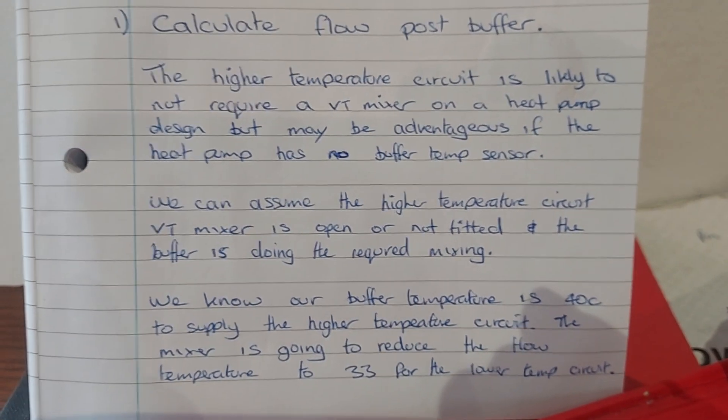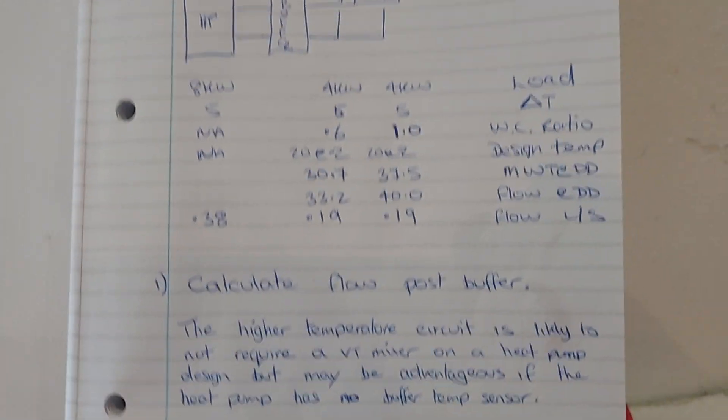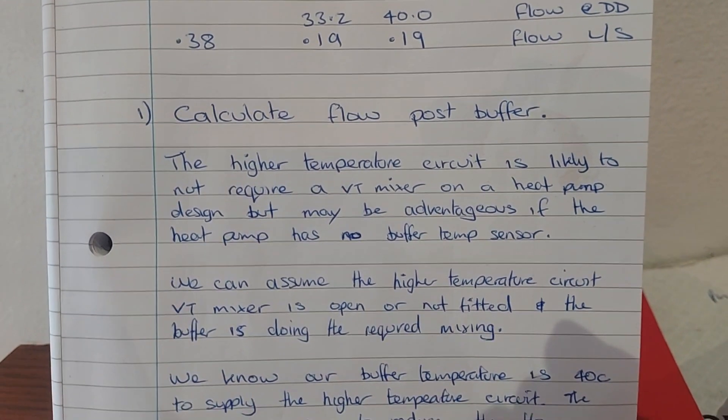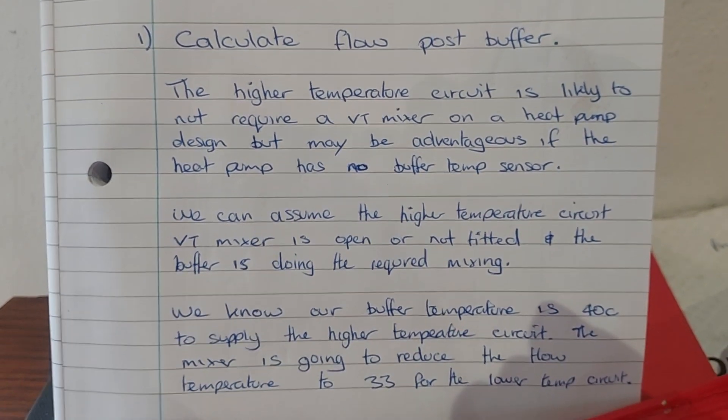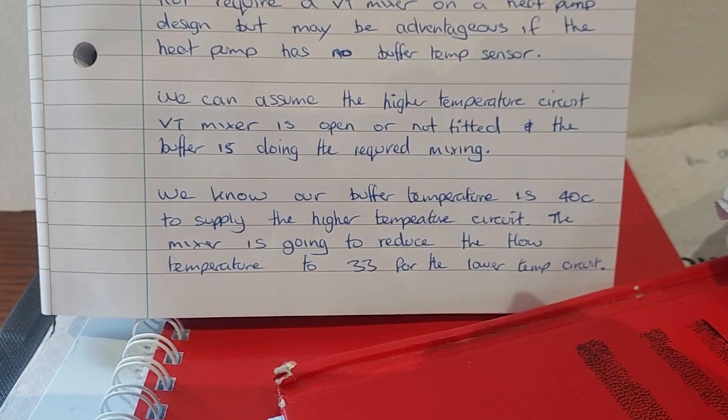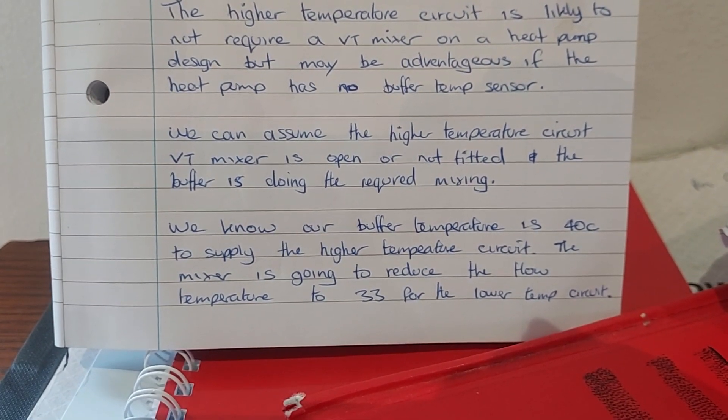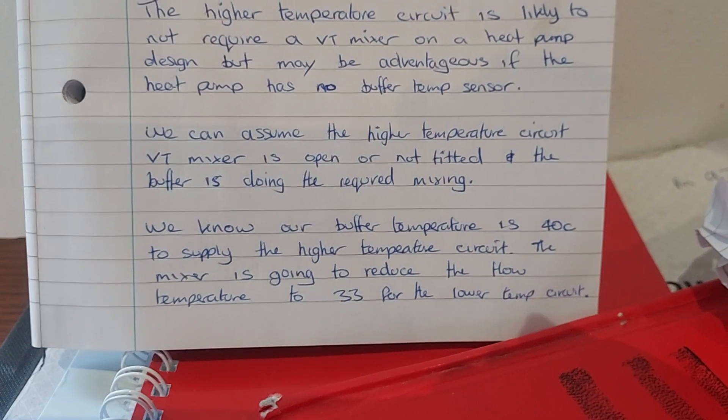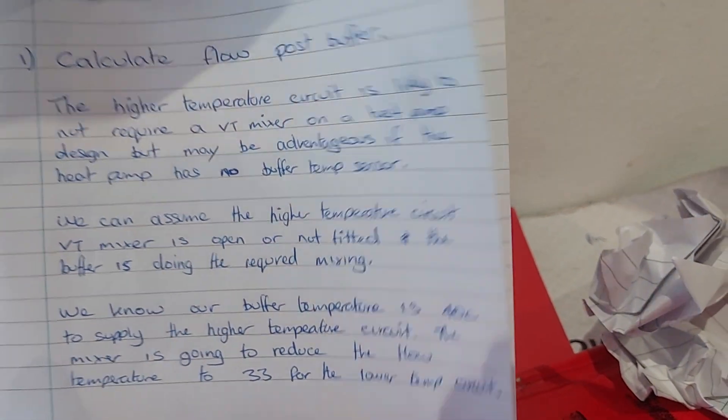We're going to calculate the flow post buffer. We want to calculate the actual flow we're going to have in this circuit here. The myth is that the flow on this site would be greater and that's not the case, but let's go through it. The higher temperature circuit is likely not to require a variable temperature mixer on a heat pump design, but may be advantageous if the heat pump has no buffer temperature sensor. We can assume the higher temperature circuit variable temperature mixer is open or not fitted and the buffer is doing the required mixing. We know our buffer temperature is 40 degrees centigrade to supply the higher temperature circuit. The mixer is going to reduce the flow temperature to 33 for the lower temperature circuit. That's our starting point for our calculations.